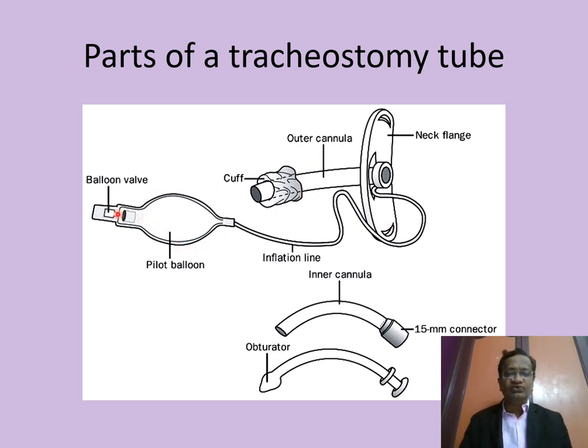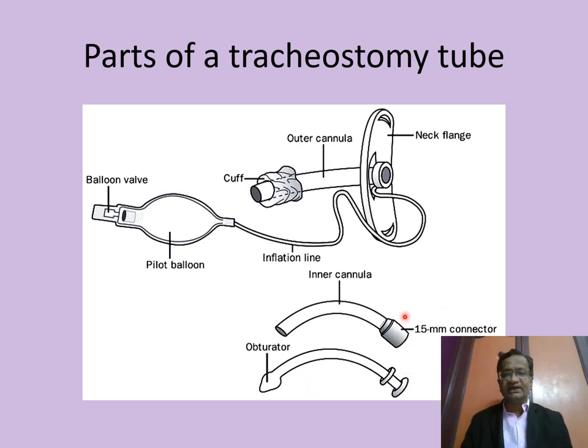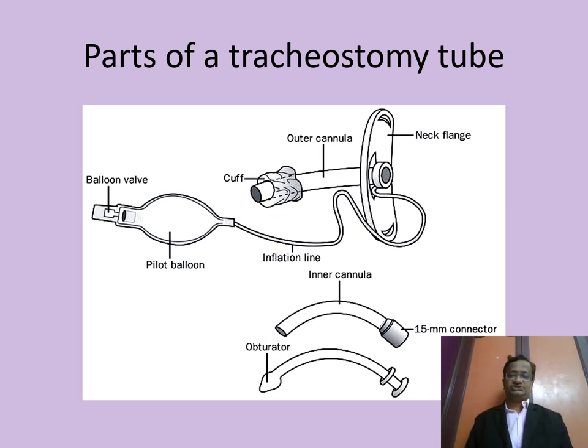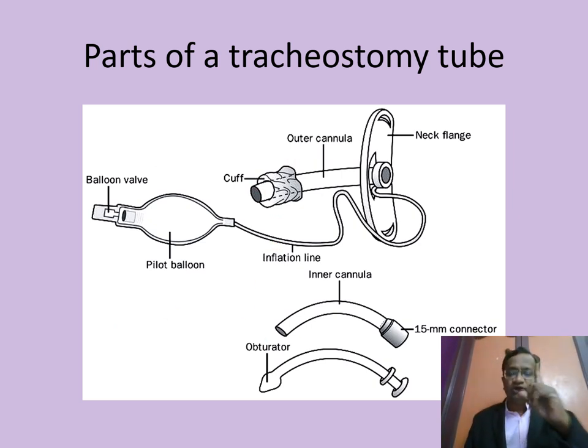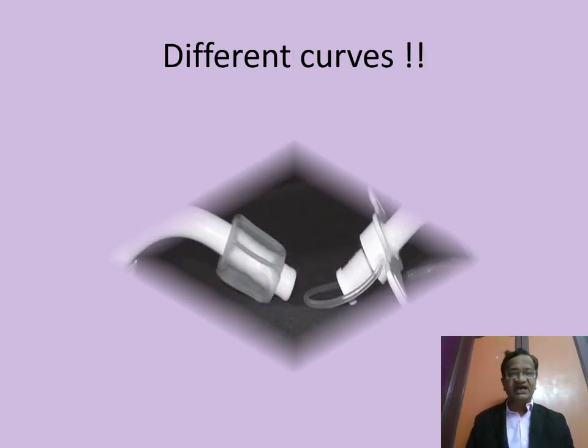Parts of the tracheostomy tube include: the outer cannula, the neck flange, the pilot balloon, the balloon valve, the inflation channel, the cuff, and the inner cannula which goes inside. Remove the obturator and connect the 15 mm connector to start ventilating. There are mono-cannula and dual-cannula tubes with different curves to suit the patient.